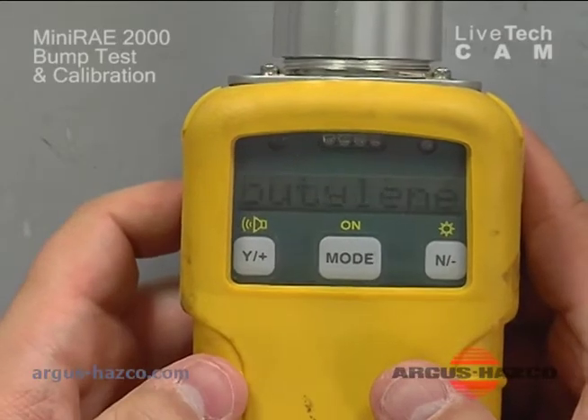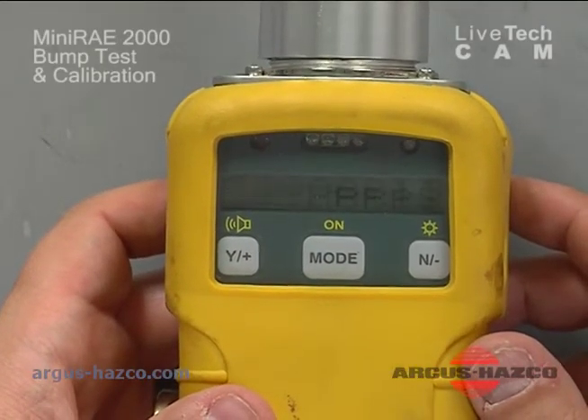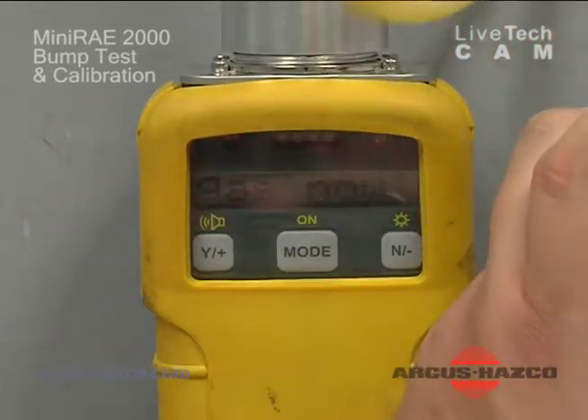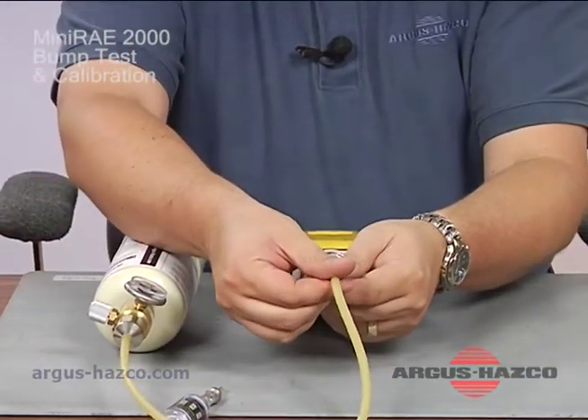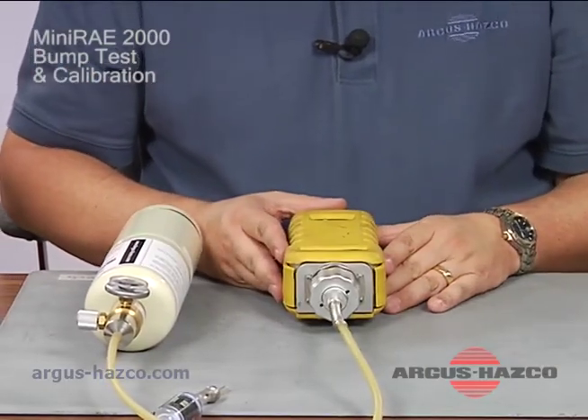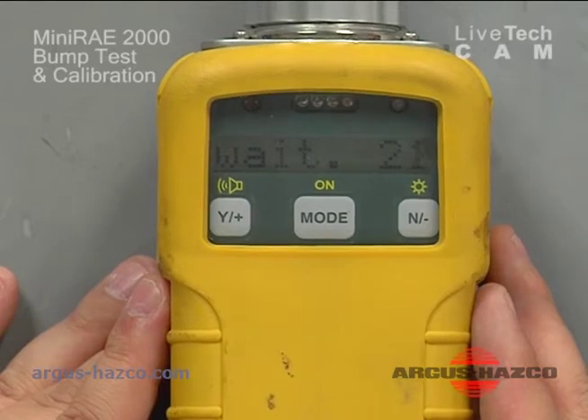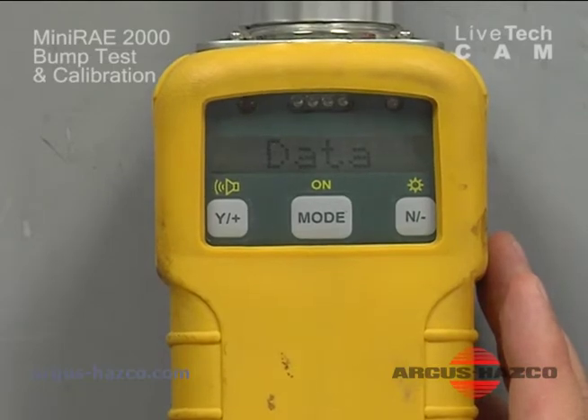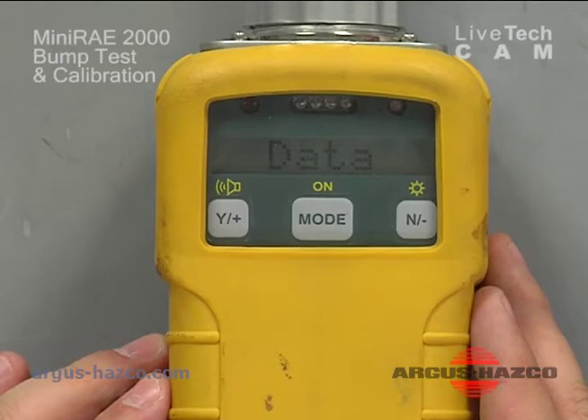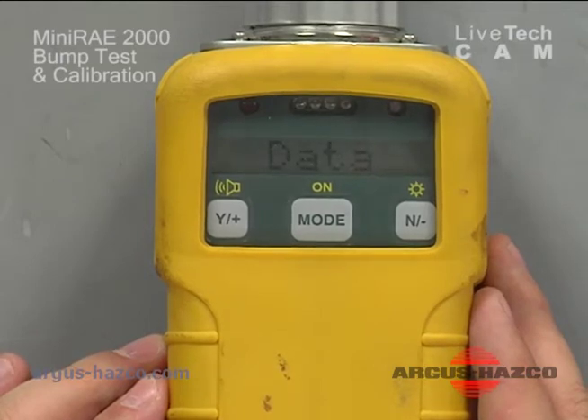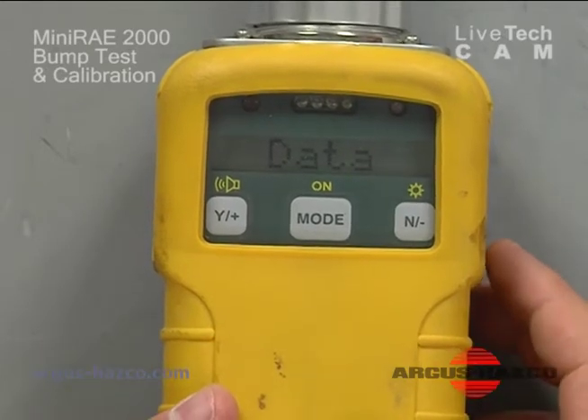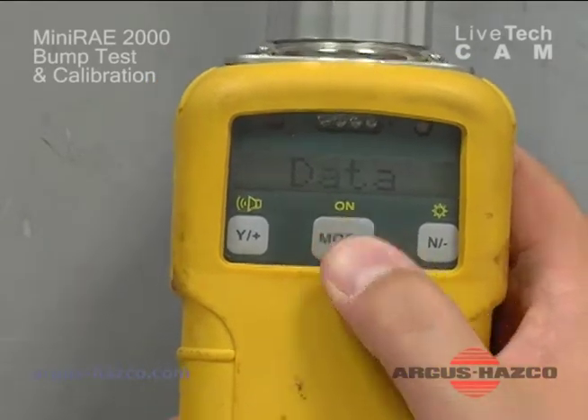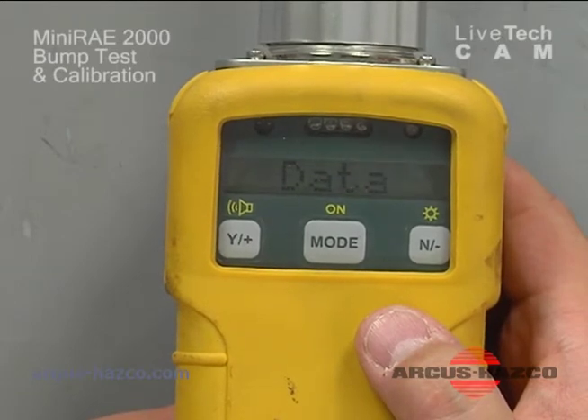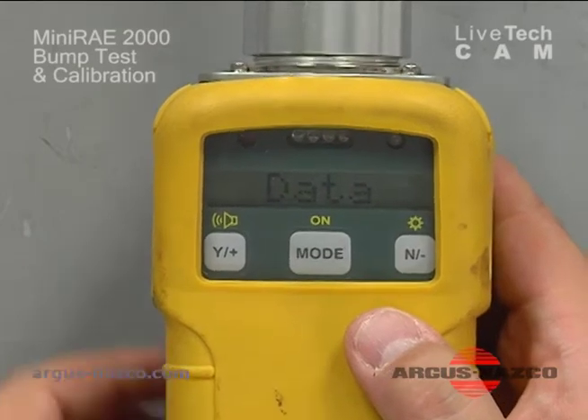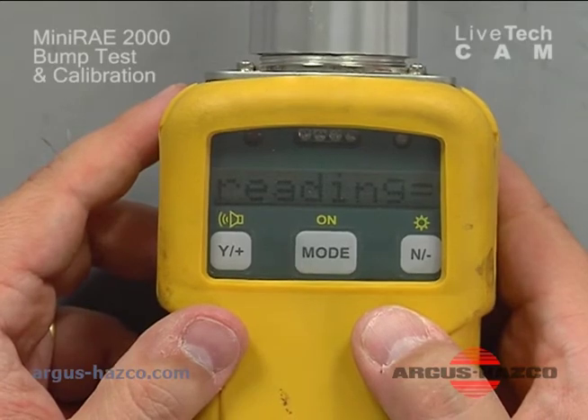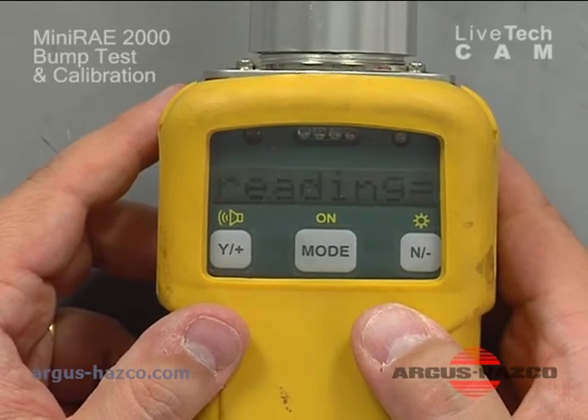Span cal, yes. Saying isobutylene. Span value equals 100, which matches your cylinder. It's saying apply the gas now. Turn your valve on the cylinder. Connect it to the front of your instrument. It's going to wait and count down, allowing the reading to stabilize to that 100 ppm. It's updating the data. It's saying the reading equals 101 ppm. So it is now calibrated.